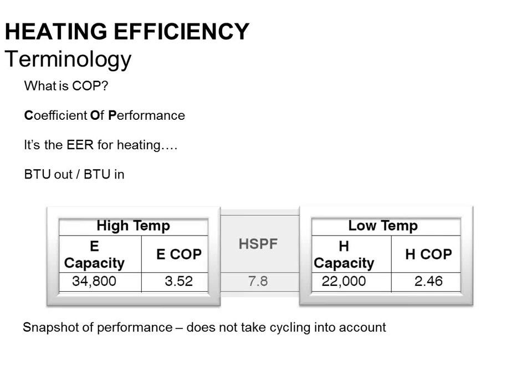If I have electric strip heat, it's basically 100% efficient. Technically, it's slightly less than that because you're losing some of it to visible light on the coil, but basically it's 100% efficient for electric strip heat at the site. Heat pumps are 250 to 350% efficient, and even when it's 10 degrees outside, it's still over 100% efficient. Heat pumps are always, always more efficient than any other heating source you have available to you.